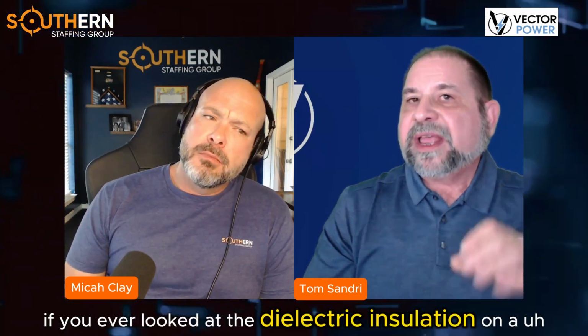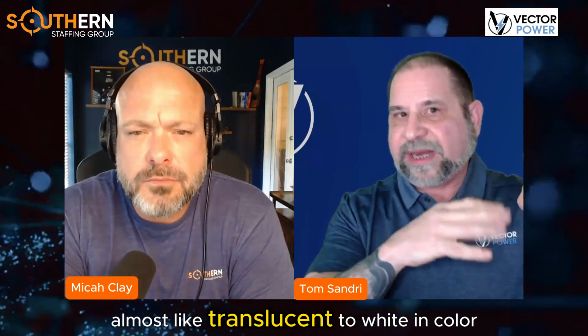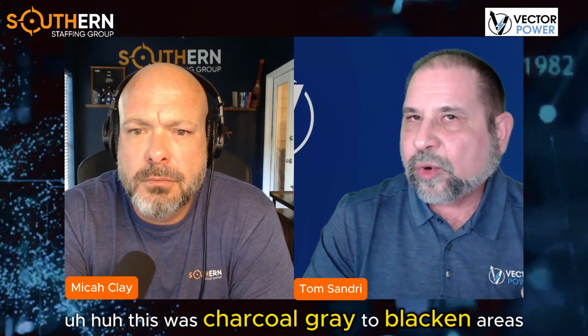If you ever looked at the dielectric insulation on a cross-linked polyethylene cable, it's very, very almost translucent to white in color. This was charcoal gray to black in areas, and if you squeezed on it, it actually was mushy to the touch. Really, extreme thermal degradation.